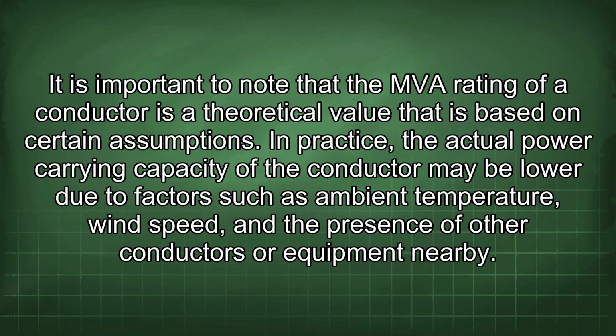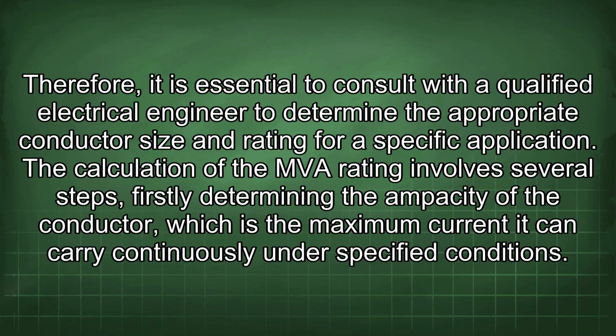It is important to note that the MVA rating of a conductor is a theoretical value that is based on certain assumptions. In practice, the actual power carrying capacity of the conductor may be lower due to factors such as ambient temperature, wind speed, and the presence of other conductors or equipment nearby. Therefore, it is essential to consult with a qualified electrical engineer to determine the appropriate conductor size and rating for a specific application. The calculation of the MVA rating involves several steps.